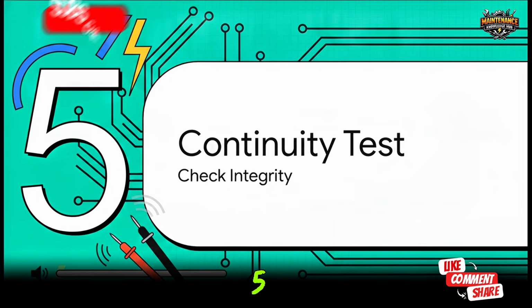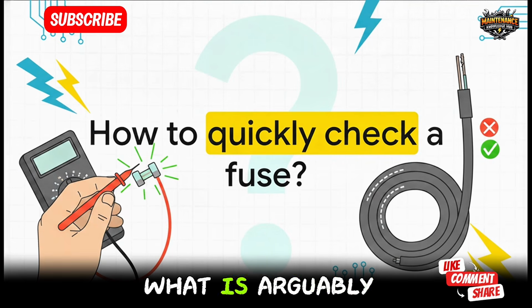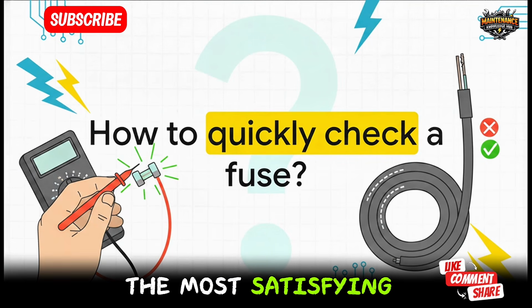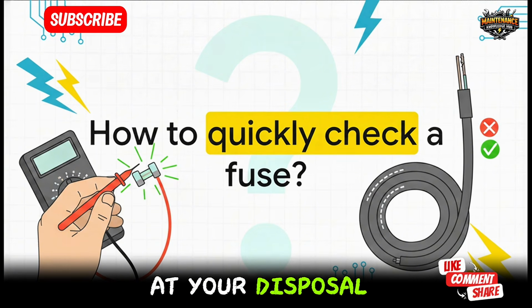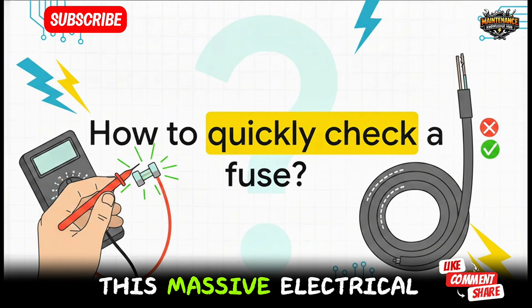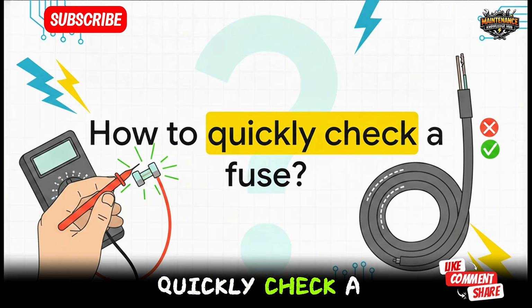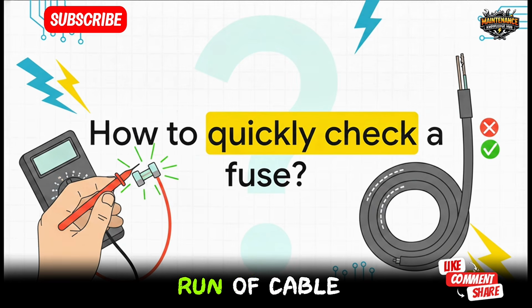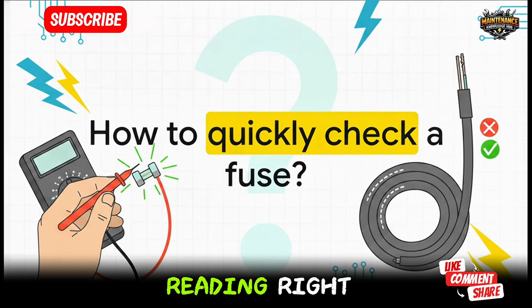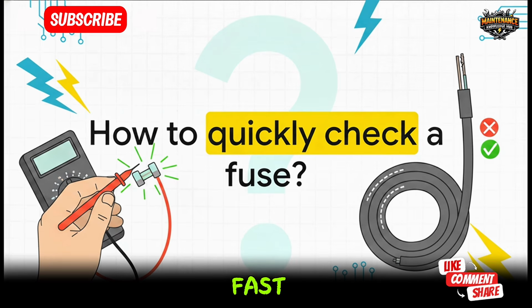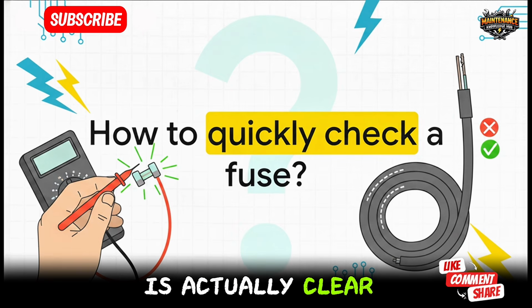Up next, Section 5, the continuity test. Okay, we've arrived at what is arguably the most satisfying sensory-driven tool at your disposal. Imagine you're out there troubleshooting this massive electrical panel. How do you quickly check a fuse or verify that a huge run of cable isn't broken somewhere hidden inside its jacket? You don't always need an exact, precise numeric resistance reading, right? Sometimes you just need a really fast yes or no answer to see if the path is actually clear.